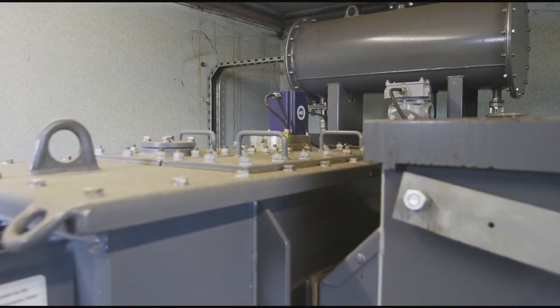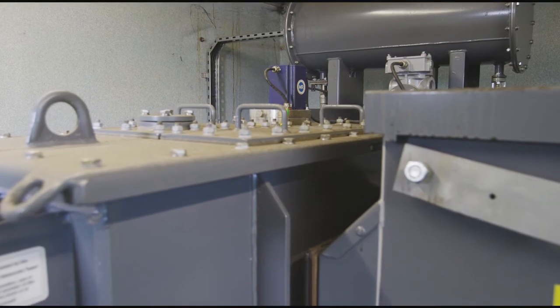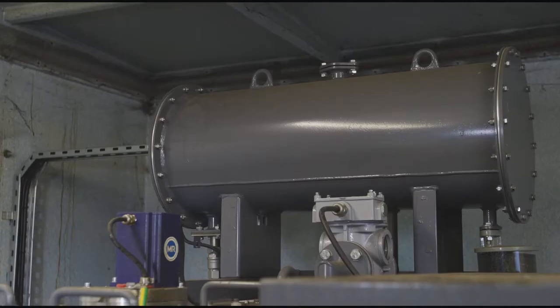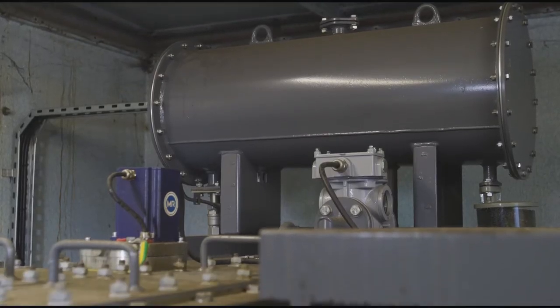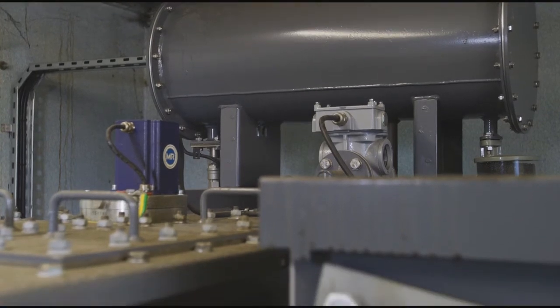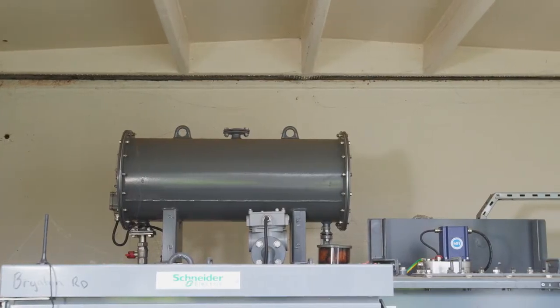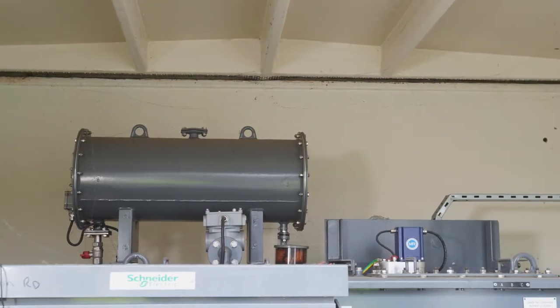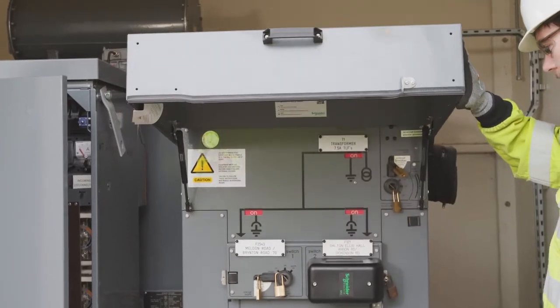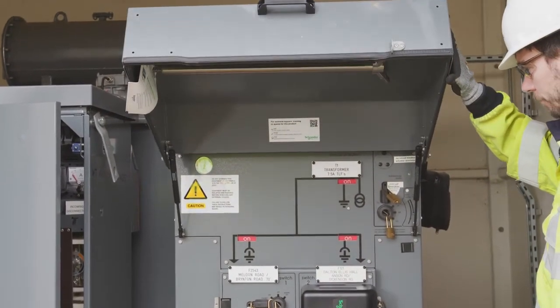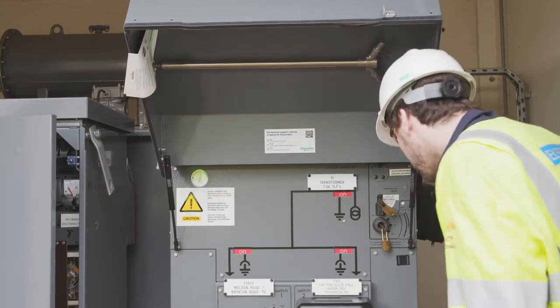Technically, what Smart Street is about: firstly, it's delivering 180 on-load tap changing transformers into our distribution substations. These are a mix of 11,000 and 6,600 volt transformers of mixed ratings, all cable connected. They'll be able to control the LV voltage by up to 20% around the nominal tap position, compared to standard transformers which only allow 10% control.